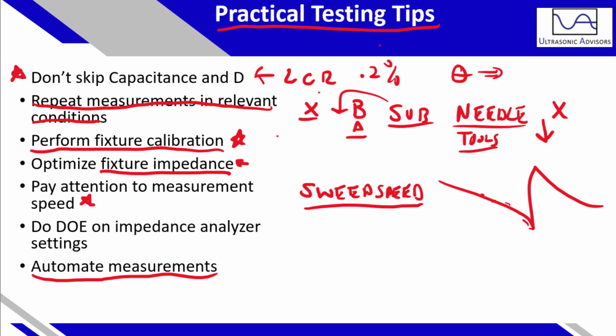If you do your measurement within 1 second or 45 seconds across the resonance and anti-resonance regions, you have to find that sweet spot that's not too long, not too short. For a high Q material, a Q factor above 200, it's important to use a larger sweep time, something like 30 seconds and larger. Basically, do a design of experiments. Create a grid of different impedance analyzer settings, and understand which settings lead to stable, accurate results.